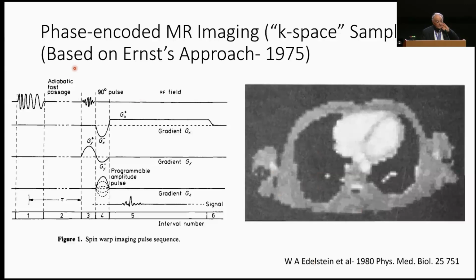And this is the diagram from that of the so-called spin warp imaging, which, instead of having a rotating set of gradients, which is sort of like having AP and lateral and oblique images in a chest X-ray, we actually use gradients to encode position. So we have an excitation pulse here designed to create the signal. We have slice selection by applying a gradient during this excitation time, in this nominal y direction. We'll have a gradient imposed during the signal detection, which is just so-called frequency encoding, which is the heart of things.